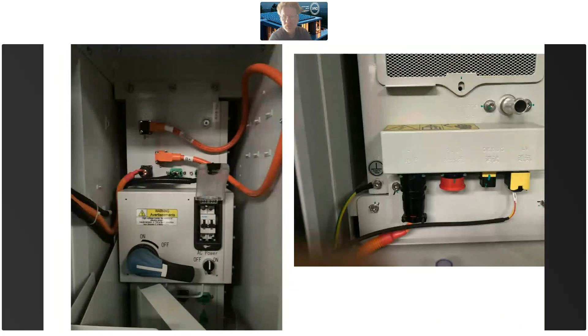These are more close-ups of the electronics and how you attach to them. They're surprisingly simple, these big batteries. It's really just those massive black cell packs wired in series, with a cooling system, feeding through to a BMS behind this plate, which makes sure everything's happy. It won't turn on if it's not happy, or if it doesn't have proper comms with the inverter. Then the contactor clicks in, and that's pretty much all there is to it. It also has safety features so it won't operate with the door open and things like that.